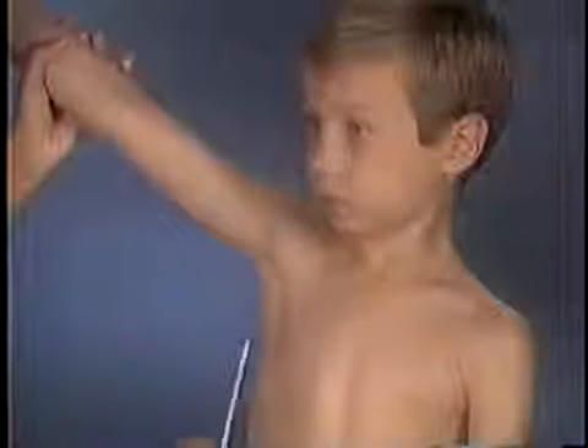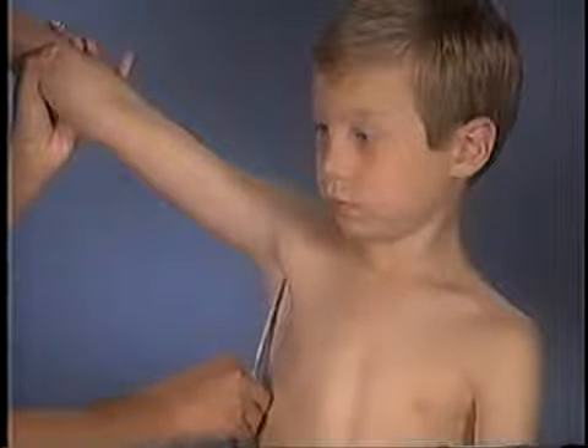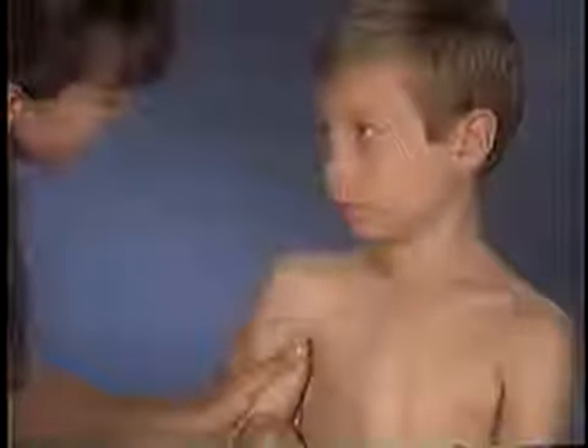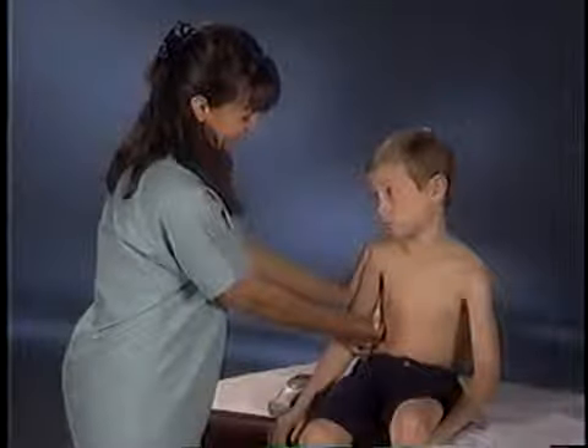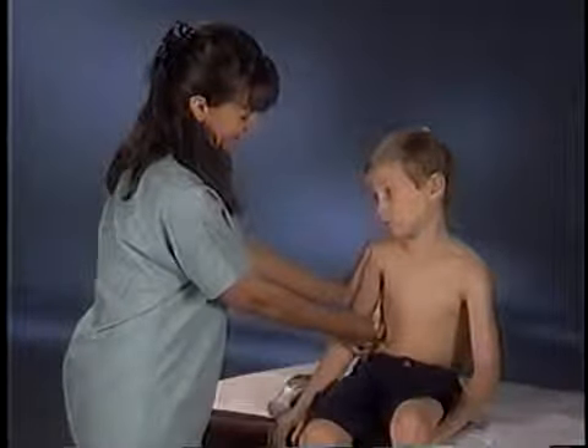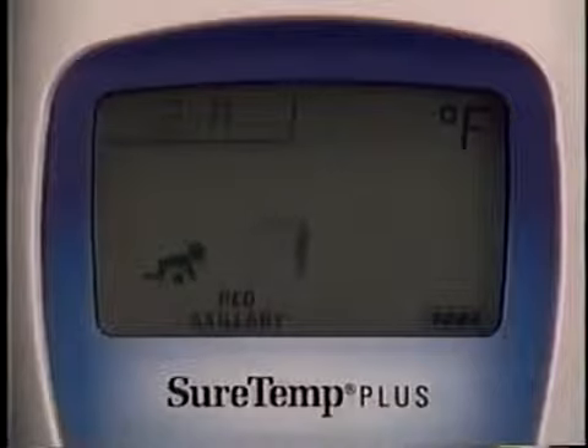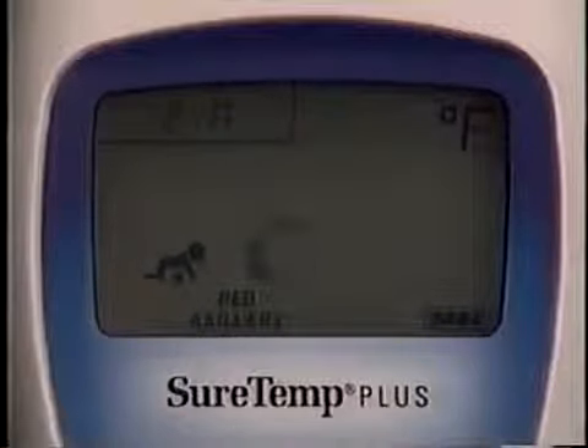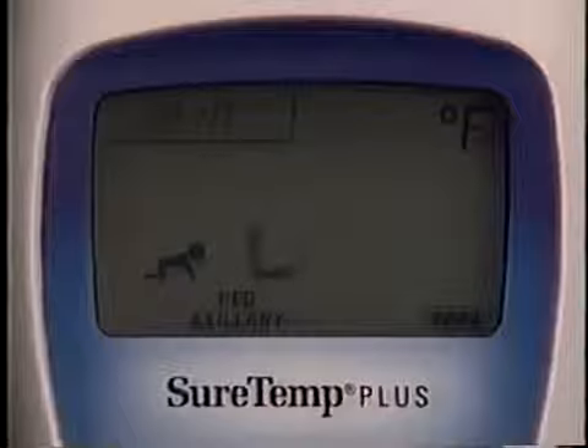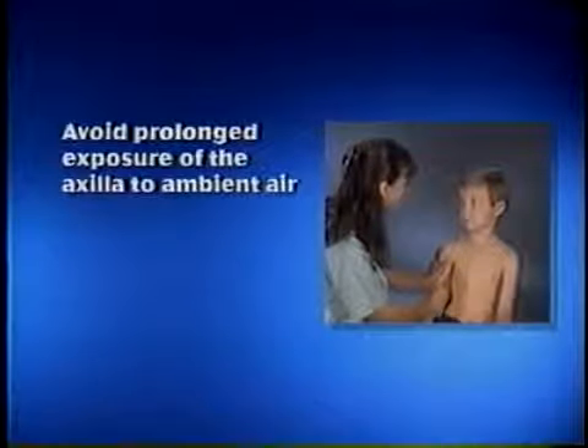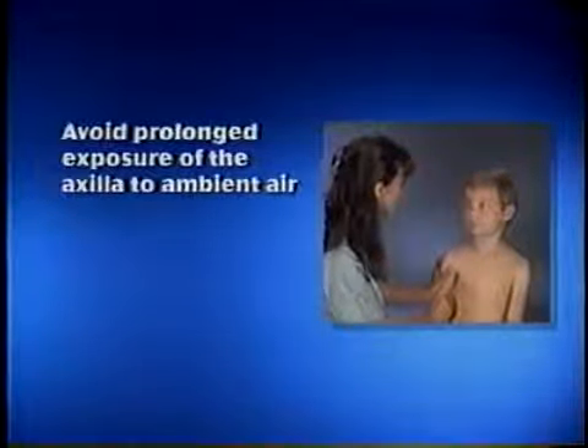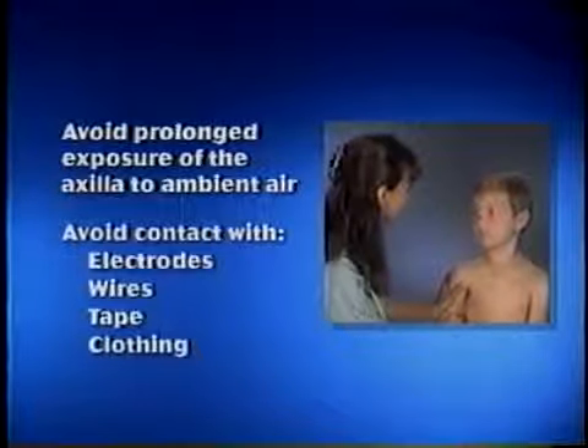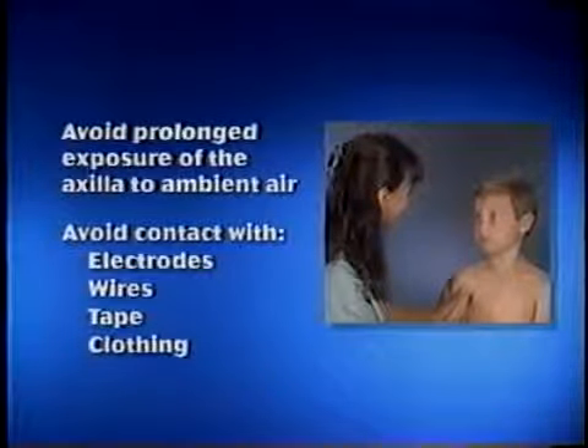Lift the patient's arm and place the probe as high as possible in the axilla, keeping it vertical or aligned with the patient's spine. Lower the patient's arm, making sure the probe tip is completely surrounded by axillary tissue, and hold the patient's arm at their side for the entire measurement, avoiding movement of the arm or probe. Walking segments appear, indicating that measurement is in progress. Prolonged exposure of the axilla to ambient air can cause inaccurate readings. You should also keep the probe tip from contacting electrodes, wires, tape, or clothing.